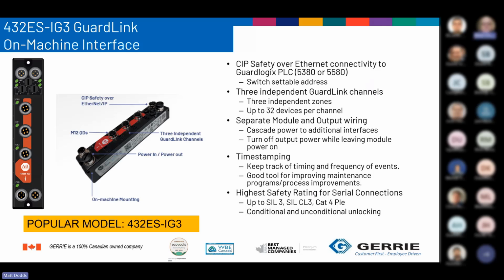So again, connectivity over CIP Safety over EtherNet/IP using the GuardLogix 5370 or 5580 PLCs, switch selectable addresses, same functions, 32 devices per channel, 3 independent zones. You can separate the mods and the output wiring, time stamping, and again, they maintain a high level of safety. One model to choose from in a nice compact housing.